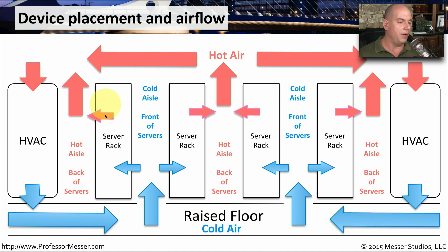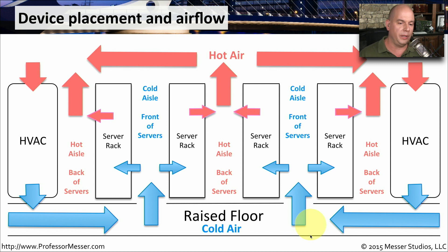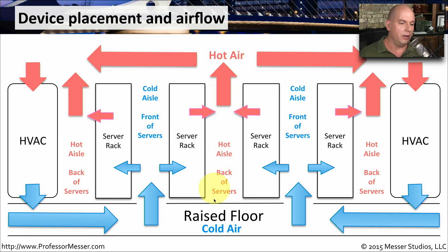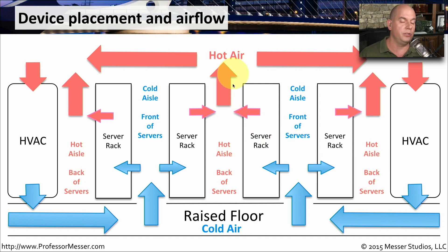Then you have all of the server racks. The server racks are designed so that cool air is being pulled in from one side of the rack, heating up that air and pushing it out to the outside of the rack. The hot aisles are connected to each other — there's a hot aisle, another hot aisle, and another. The hot air then goes to the top of the ceiling, and the entire process begins again.